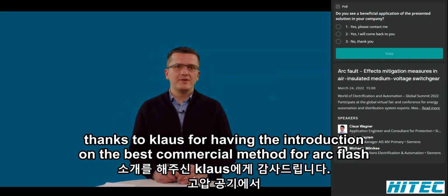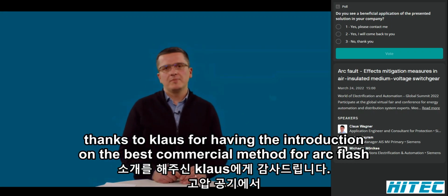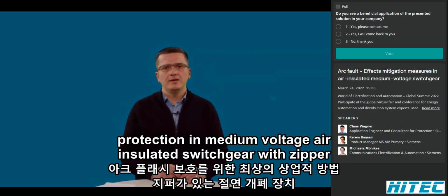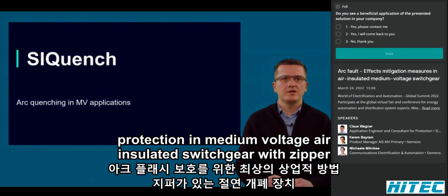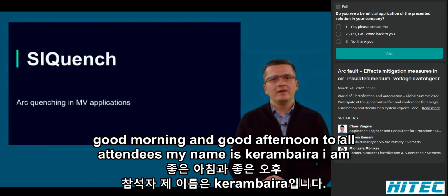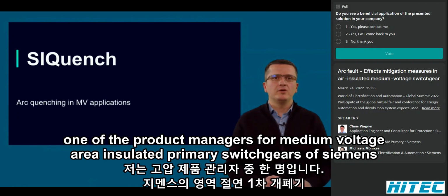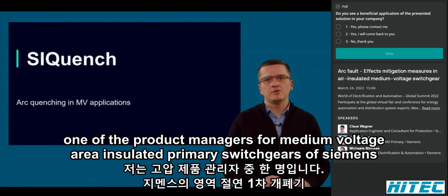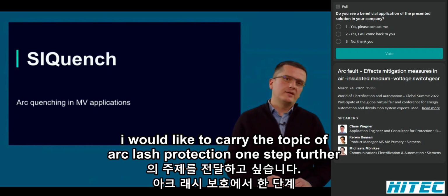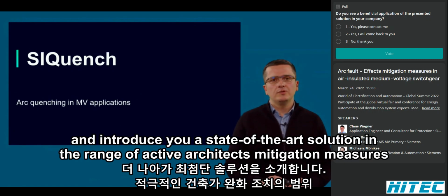Thanks to Klaus for having the introduction on the best conventional method for arc flash protection in medium voltage air insulated switchgear with SIPROTEC5. Good morning and good afternoon to all attendees. My name is Kerem Bayram. I am one of the product managers for medium voltage air insulated primary switchgears of Siemens. I would like to carry the topic of arc flash protection one step further and introduce you a state-of-the-art solution in the range of active arc effects mitigation measures.